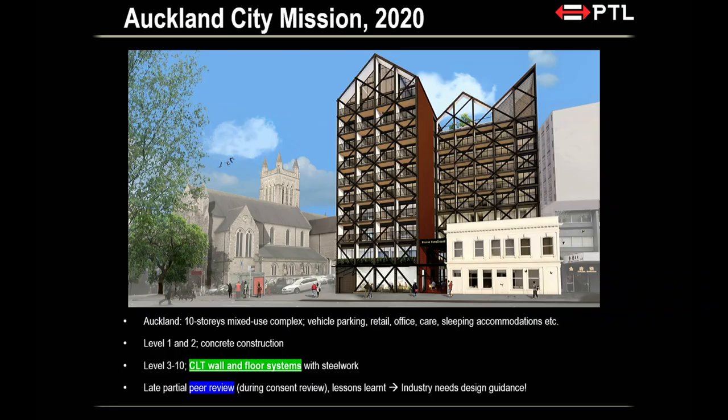You need a specific system to limit the temperature of the timber to no more than 300. They're putting normal GIB plasterboards, standard plasterboards. It's going to fall off in 15 minutes, basically, right? So we managed to convince the designer: look, you need to add a few Fyreline here, a few Fyreline there, get to this particular performance and get it done.